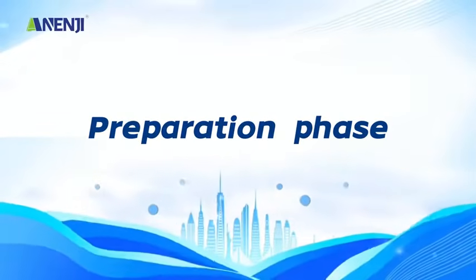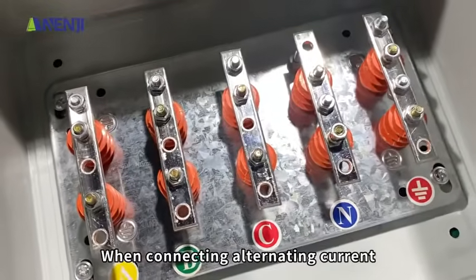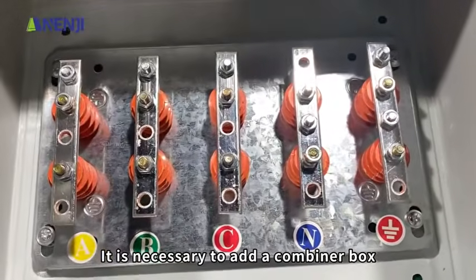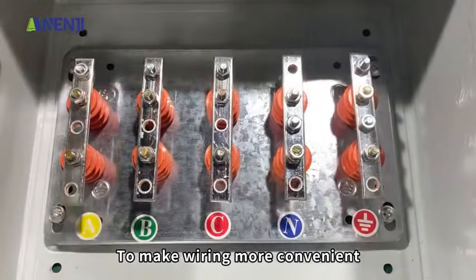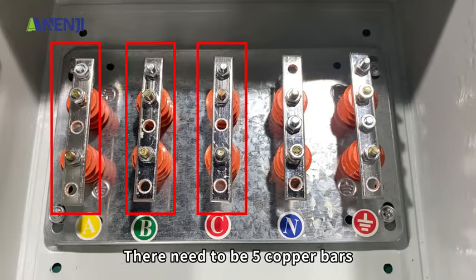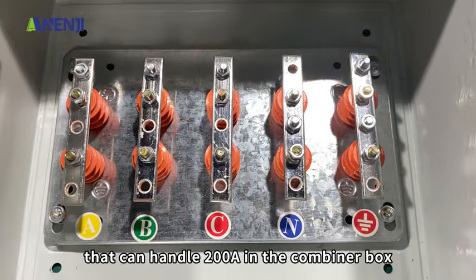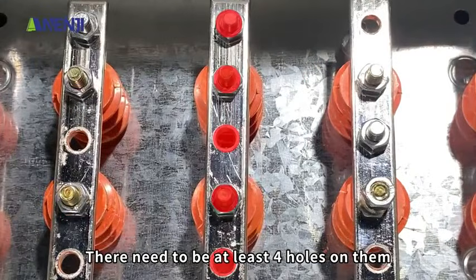Preparation phase. When connecting alternating current, it is necessary to add a combiner box. To make wiring more convenient, there need to be 5 copper bars that can handle 200A in the combiner box. There need to be at least 4 holes on them.